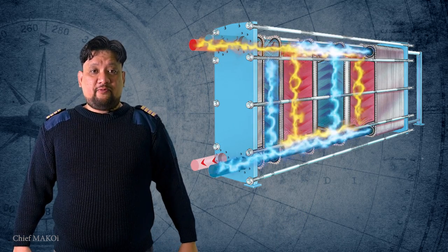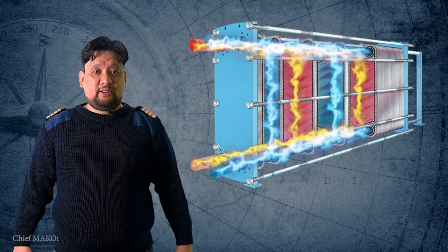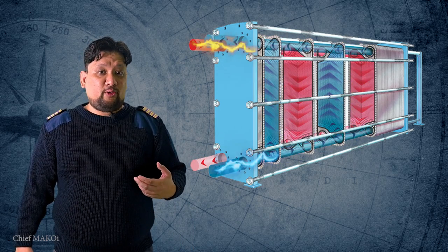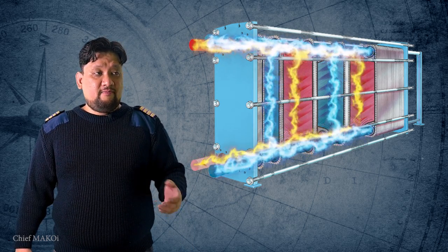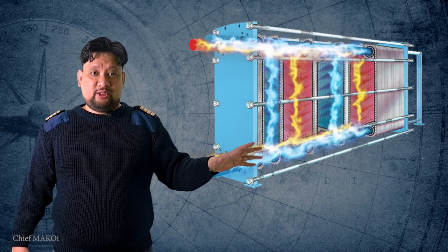The centralized cooling system offers a lot of advantages over the direct seawater cooling like less corrosion and lower maintenance cost. However, the initial cost of installation will be relatively higher compared to that of direct seawater cooling. In any case, both systems are effective in serving their main purpose, which is to absorb unusable heat from the engines and eject it into the sea.